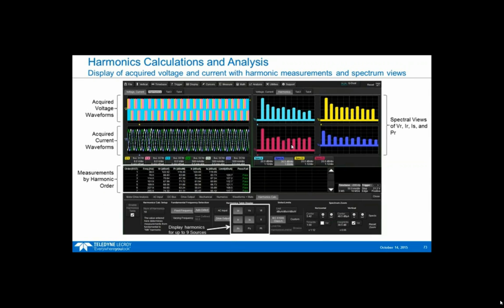We also have the ability to look at the measurements for the distortion by harmonic order. This is our harmonic order table. It shows, in this case, 1 through 7, and then there's a slider bar you can go up to 50 or so, depending on the mode you've chosen, sometimes a little bit more. It displays the frequency, and depending on what you've chosen in the table display, you can look at up to 9 of these, covering all 3 voltages, currents, and powers of a 3-phase system on either the AC input or the drive output at one time, or you could just choose to look at one of them. It's really up to you.